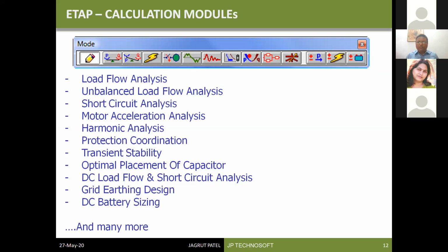So to size this component, we need to perform several calculations. The second stage, for example, when we are planning an industry, a transformer is required. To know the size of the transformer rating, the KVA rating, we need to perform a transformer sizing calculation. For that, tools are available. Similarly, the transformer is connected with HT cable. On the secondary side, there will be bus bars and LT cables. So to know the size of all these components, we need different calculations.